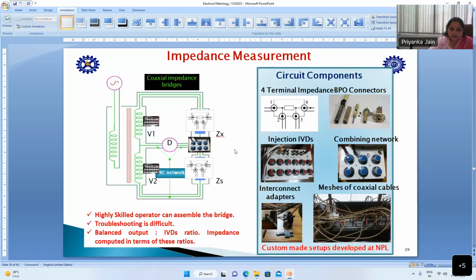Coaxial measurement: if we are talking about impedance measurement, it's not as simple as Ohm's law because many factors come into the picture. Here you can see the IVD, inductive voltage divider, our AC voltage reference standard. If we have to divide some AC voltage, we put IVDs in the circuit. It will precisely divide that voltage up to the level of 1 in 10^8. So we maintain these IVDs here for precision impedance measurement, and we make this bridge. If we make some interconnects, there should be a combining network which balances all the parasitic capacitance or inductance in the circuit. So it eliminates the impact of these interconnects, and the standard impedance is defined in four-terminal combination to get precise measurements.